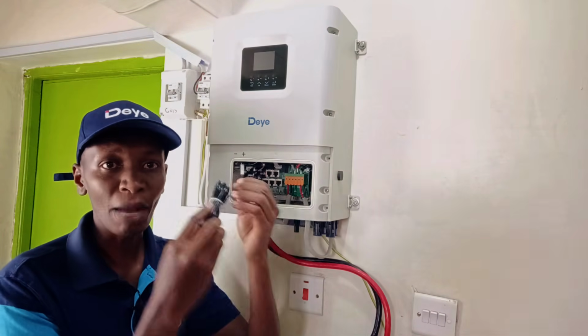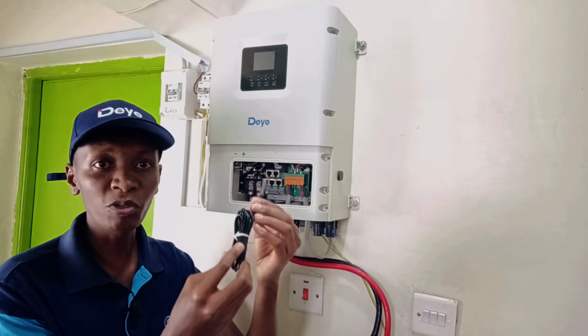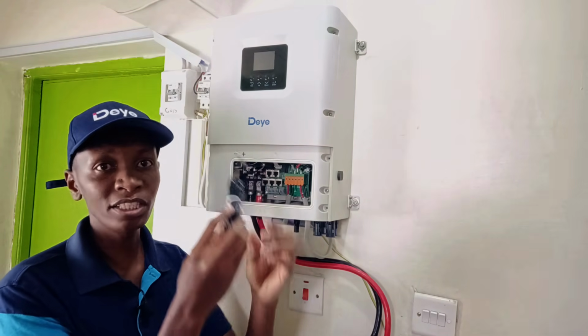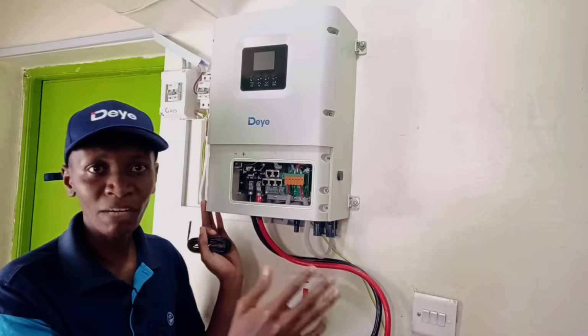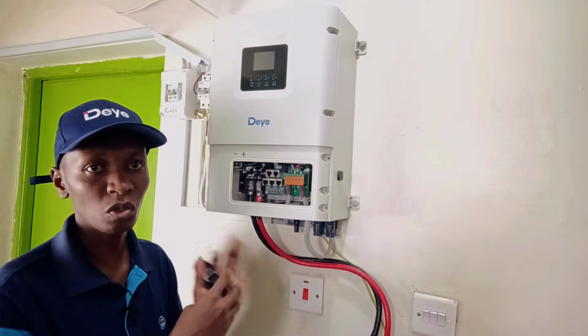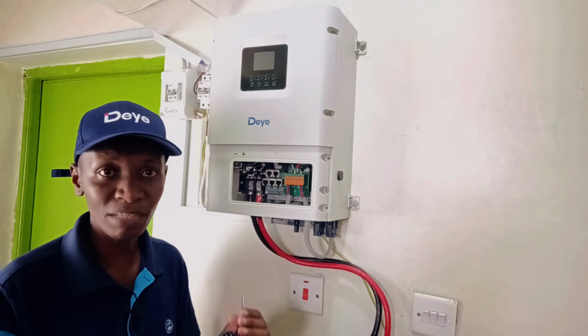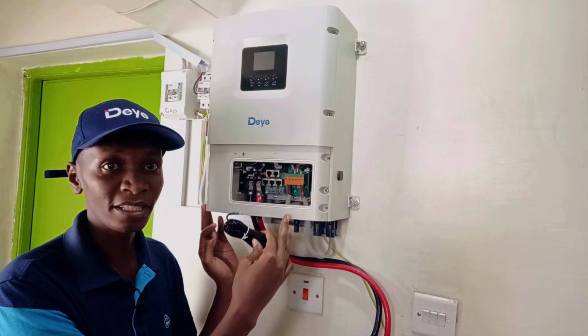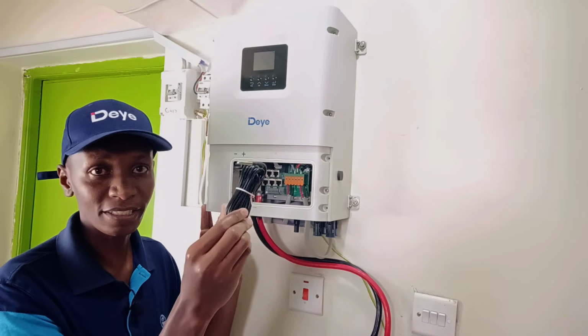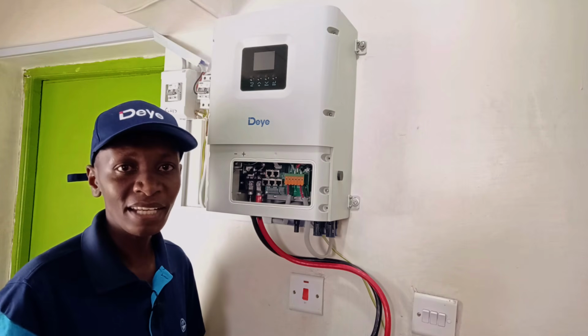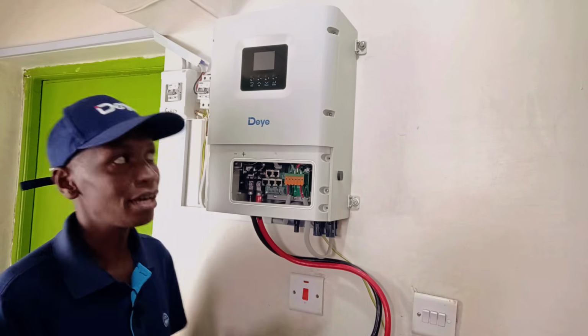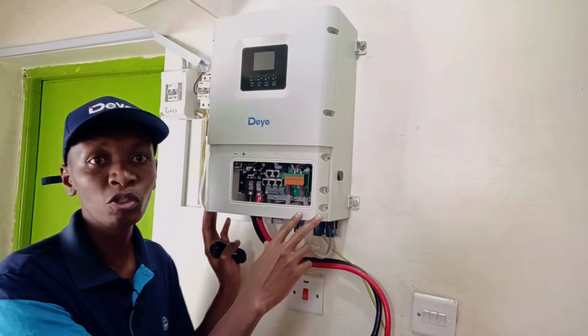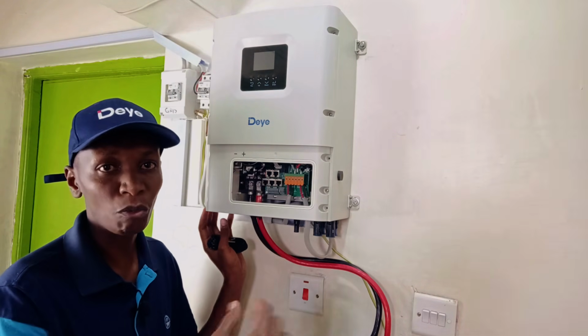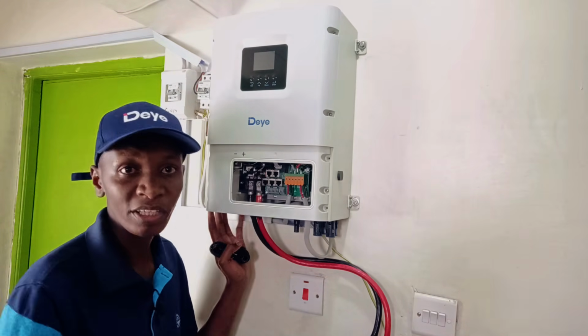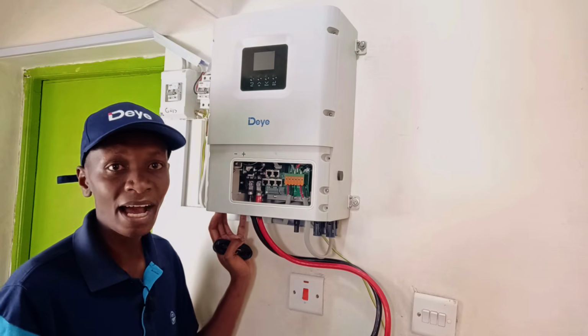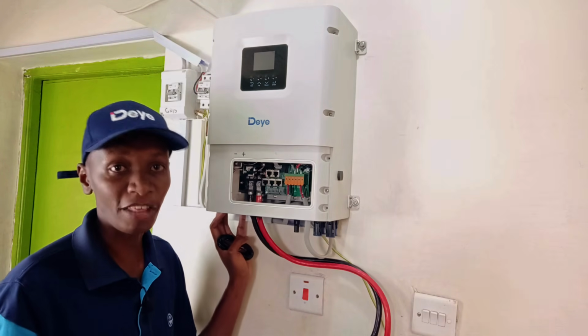Number 5 and 6 are for connecting a battery temperature sensor, and this is if you are using lead acid batteries. I do not need to use this because my inverter and my lithium battery have a communication between them, so I do not need to use this. But if you have lead acid batteries, then the inverter needs to know if they are overheating, and this is the temperature sensor for that. And finally, number 7 and 8 are for connecting a current transformer coil. This inverter didn't come with that gadget, but that is usually to track how much load you are using from your grid. You can watch this whole installation in my second video of this Deye inverter and battery series. Check the video description for that video.